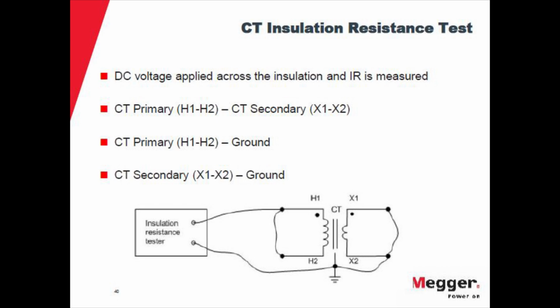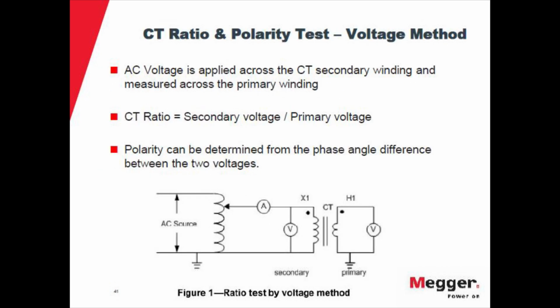Here we can see the insulation test. So basically you have your CT, you connect the primary to the secondary, and you perform the test. Then you change the leads and you do primary to ground and secondary to ground. So there are 3 different tests that you perform on the CT for the insulation. For the CT ratio and polarity, you apply voltage to the secondary winding of the CT, and you measure the induced voltage on the primary side. So this is performed with an AC source. The previous one was a DC source.